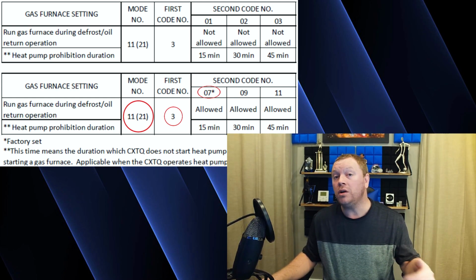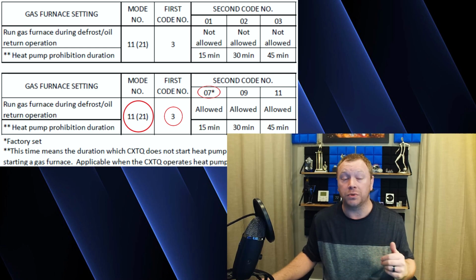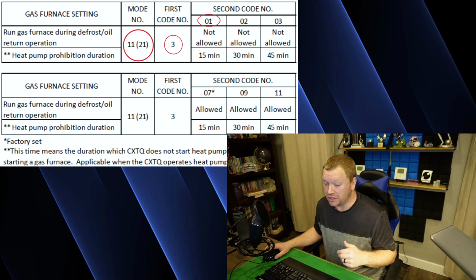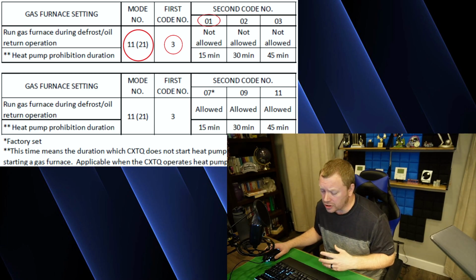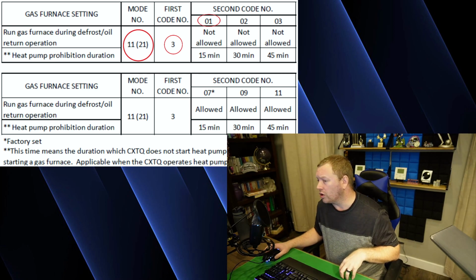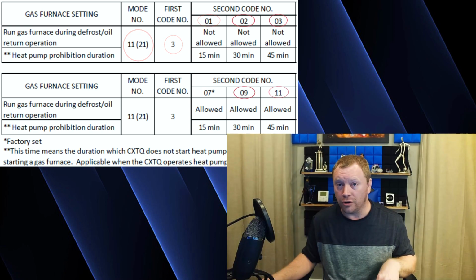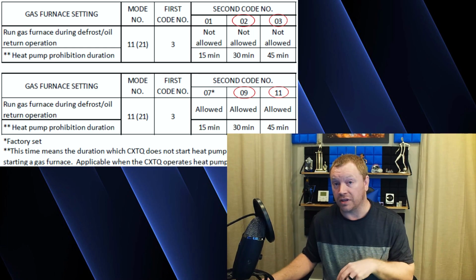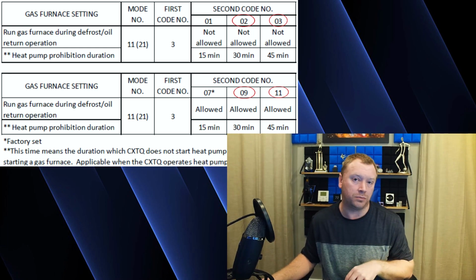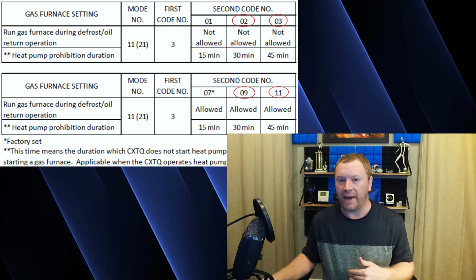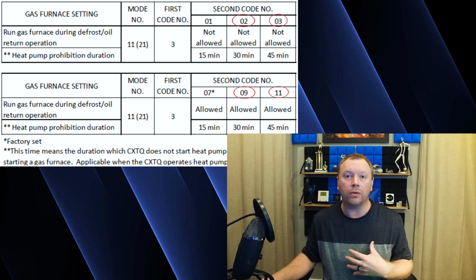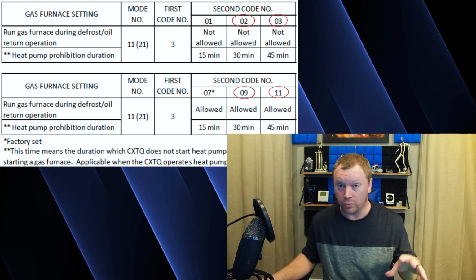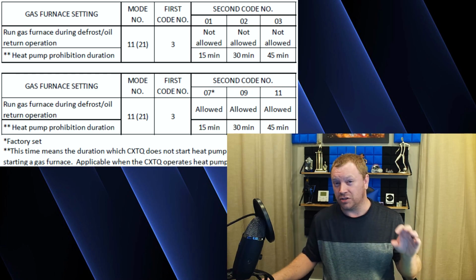If you do not want to run the gas furnace during defrost, you would change this to mode 21 setting 3-01. Now, if you're looking at the installation instructions, I'll put a snippet up here so you guys can see it as well. You'll see that there are additional options for no and for yes when you're running the gas furnace during defrost or not, and that is simply just how long you want that heat pump to be locked out for. I go ahead and I just leave it at option 7 or option 1 because defrost is so short, and I know we're going to talk about my preferences later.